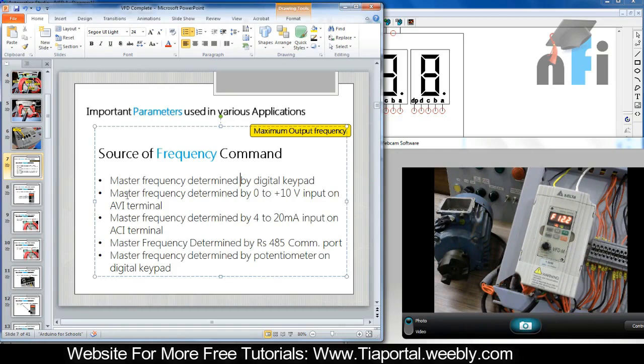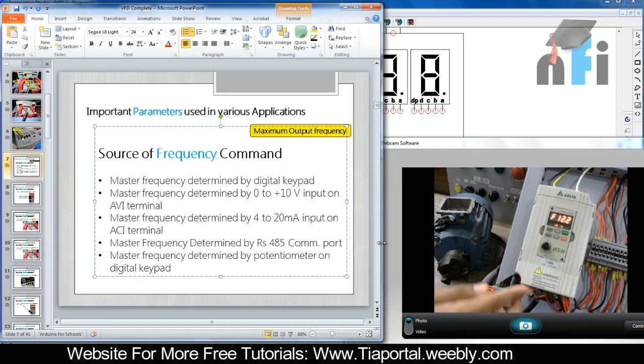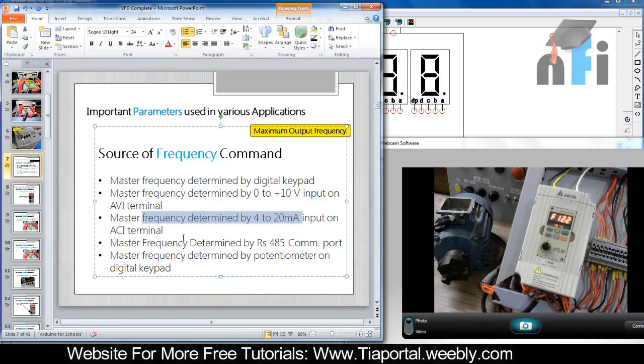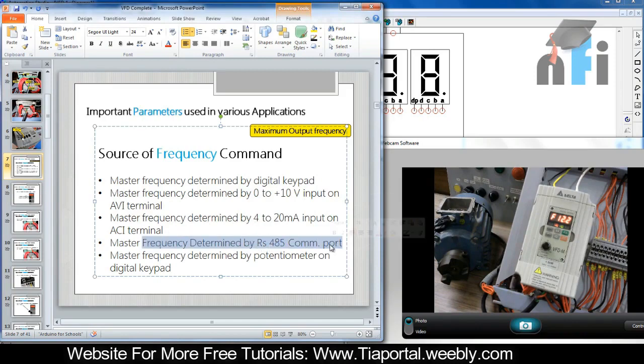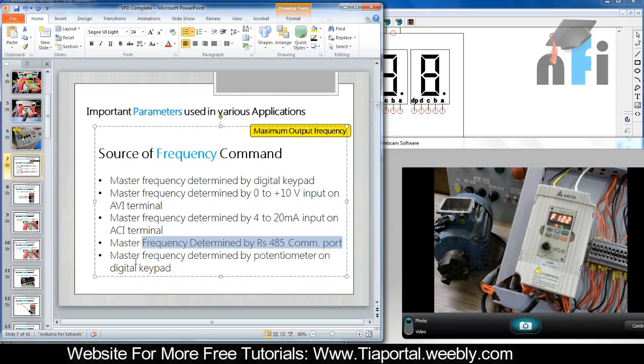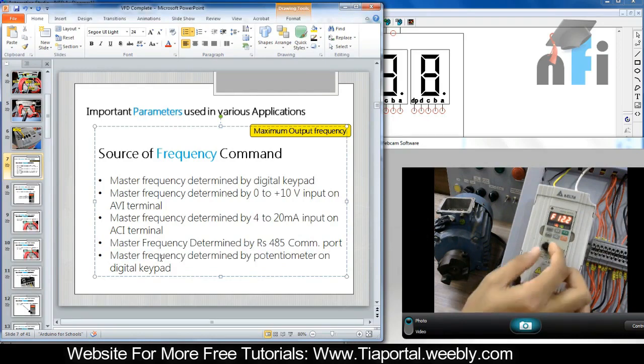The second option says master frequency determined by 0 to 10 volts on the AVI terminal. By supplying voltage of 0 to 10 volts on the AVI terminal, we can control the speed. Third is frequency determined by 4 to 20 mA on ACI terminal, as shown in the last video. Fourth is master frequency determined by RS-485 communication port. The last option is master frequency determined by potentiometer on the digital keypad.